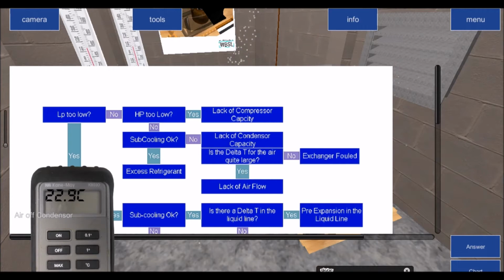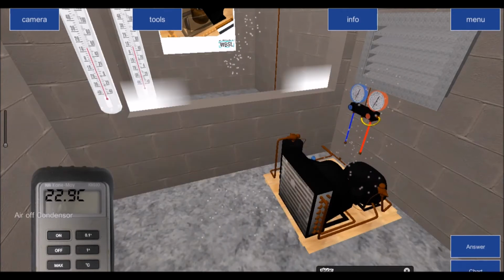So when we go back here and it says, is the delta T quite large? No. Then it's down to a heat exchanger fouled. So in other words, if we were doing this for real, you would probably notice that this is caked in dust, because this unit is actually sitting on the floor. This is a bad place to put a unit, because as soon as the shopkeeper comes along and starts sweeping the floor, the dust is going to be sucked up into the fins and so on. So normally what we would do with this would be facing the other way.